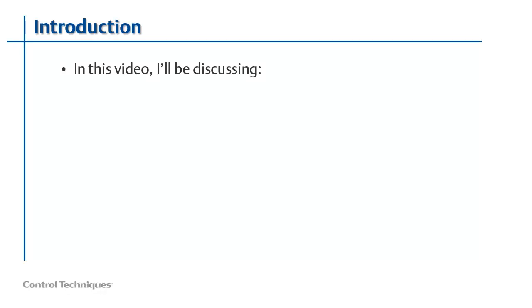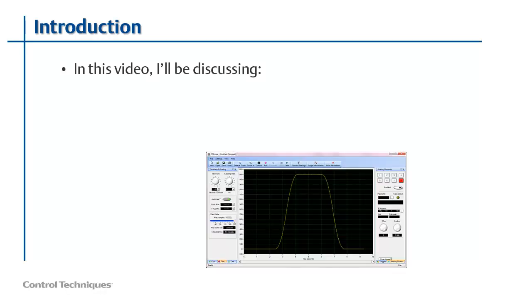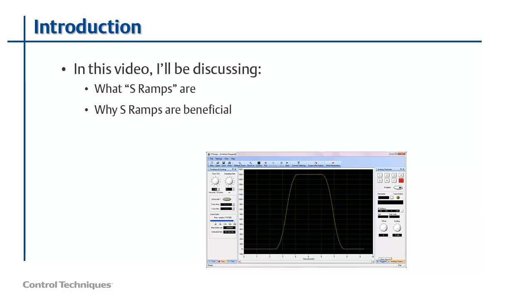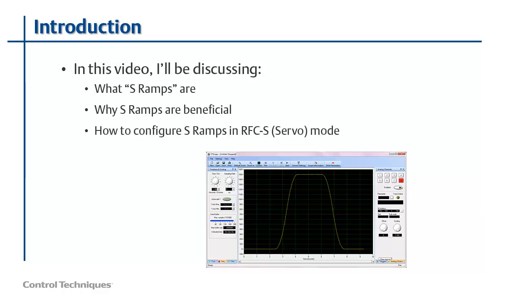In this video, I'm going to discuss what is called S ramp acceleration. S ramp acceleration is an option in all of our drives, starting with the Unidrive M100. This mode of acceleration offers an advantage over linear acceleration in most electromechanical systems. After we've learned what S ramps are and why they are beneficial, I'll then show you how to configure them in a Unidrive M700 that is operating in RFC-S or servo mode. So if you're ready, let's get started.